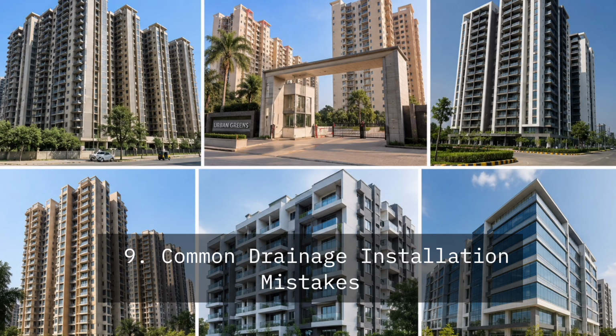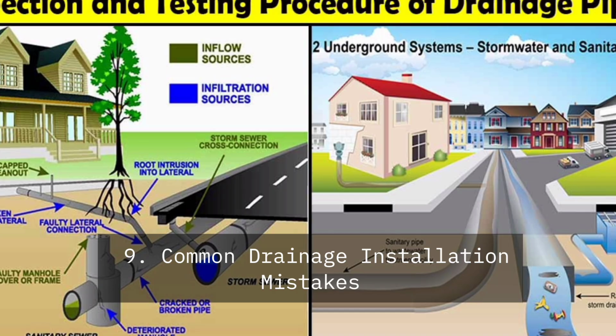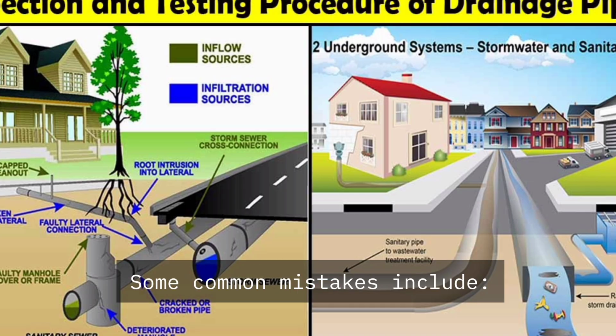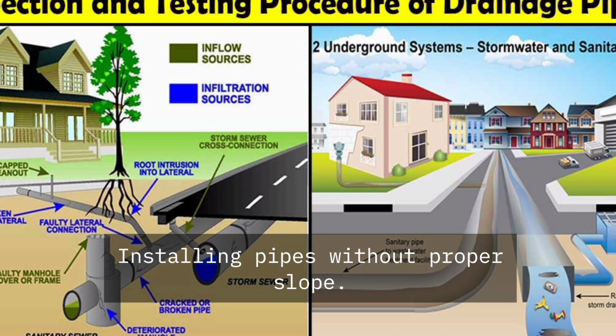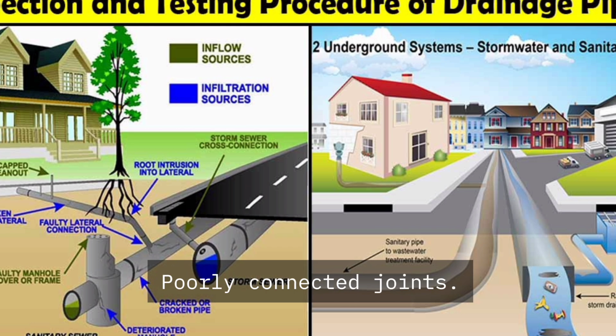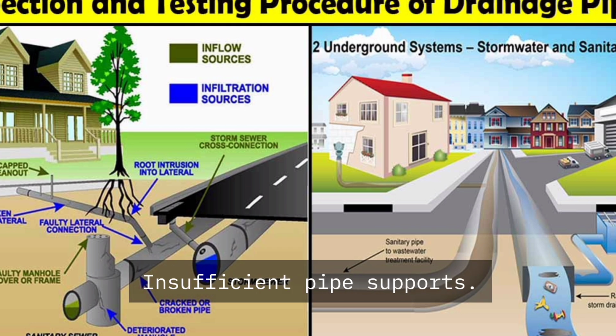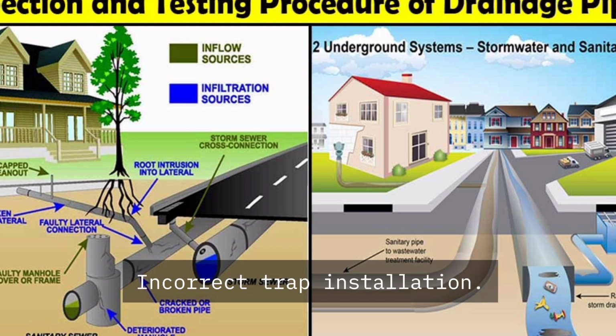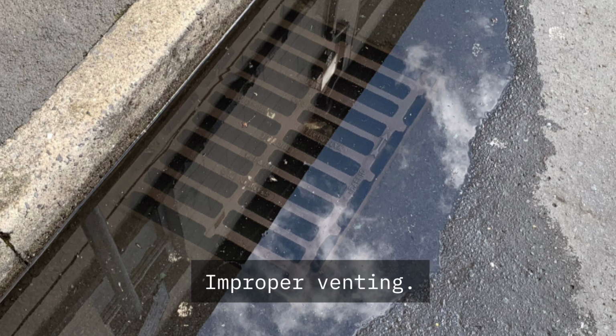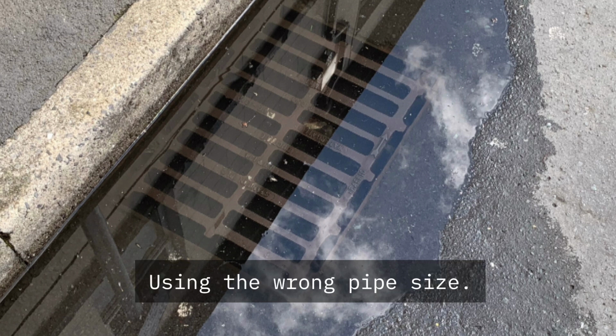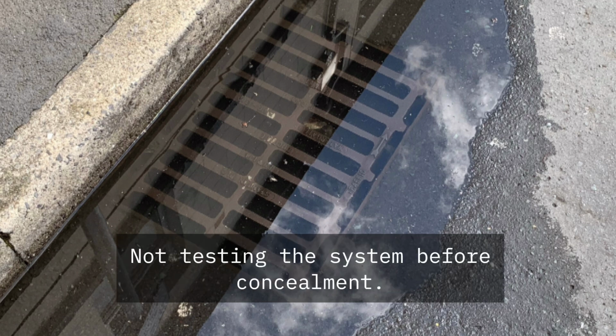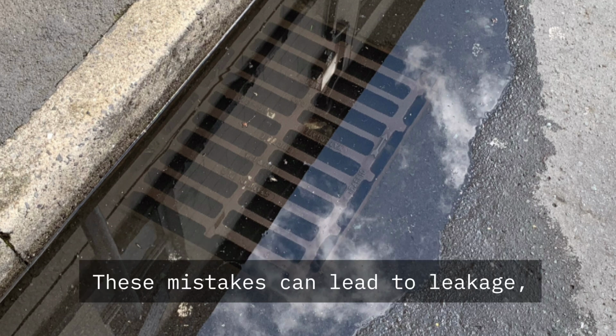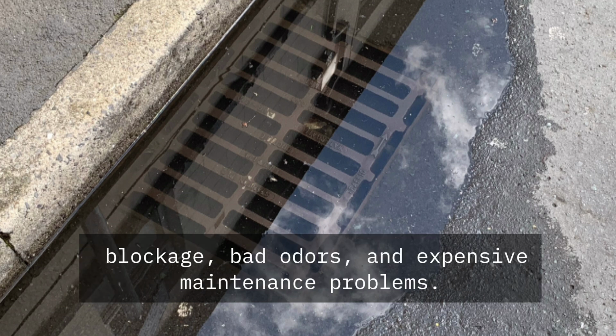9. Common drainage installation mistakes. Some common mistakes include installing pipes without proper slope, poorly connected joints, insufficient pipe supports, incorrect trap installation. Missing cleanouts, improper venting, using the wrong pipe size, not testing the system before concealment. These mistakes can lead to leakage, blockage, bad odors, and expensive maintenance problems.